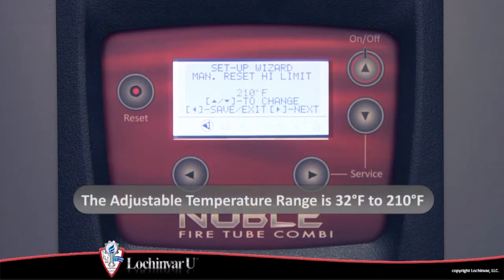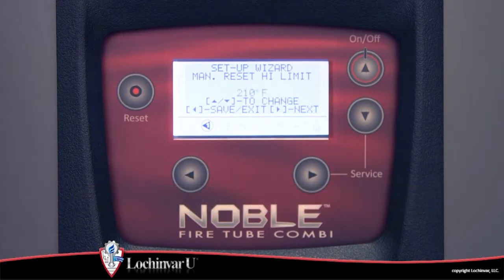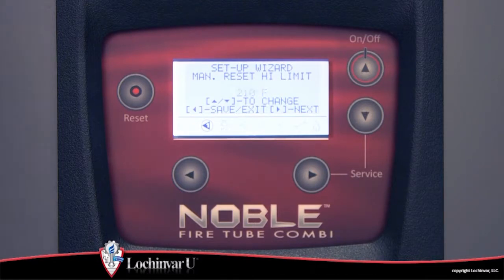The adjustment range for this parameter is 32 degrees Fahrenheit to 210 degrees Fahrenheit. The setting of this parameter should be set higher than the setting of the auto reset high limit parameter to avoid nuisance lockouts.